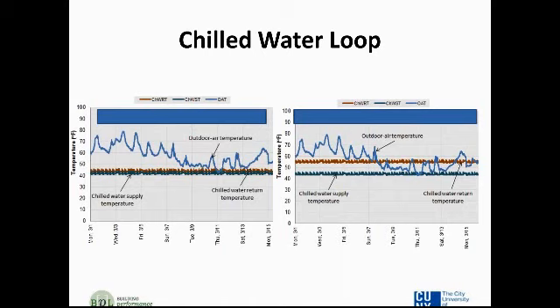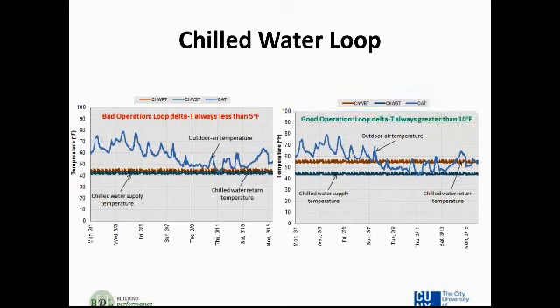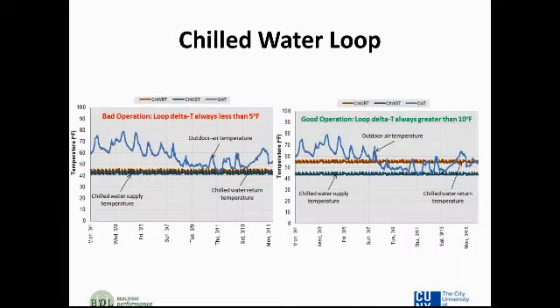A couple more examples. Here's another one where we look at the chilled water loop in your chilled water plant. On the left-hand side, you can see the outdoor air temperature starts out at 60, heads all the way up to 80, and then drops down into the 40s at one point. Our chilled water supply and our chilled water return temperatures are plotted all day long for this entire 1 week period. And you can see that the delta T, the change in temperature between the chilled water supply and the chilled water return temperature, is very low. It's only a few degrees.